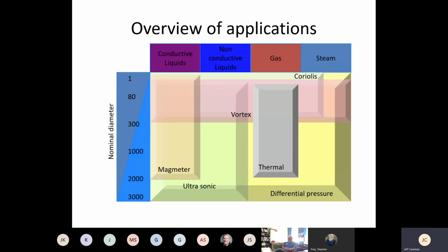So we take all these meters and we can kind of put it into a chart and look at some of our solutions that we have out there to offer. Under conductive liquids, you can see a mag meter really exists in this world. Conductive liquids only, has some limits on temperature, but really has unlimited size ability. We manufacture magnetic flow meters from a 1/12 of an inch on up to over 100 inches. I think 108 right now is the biggest one that we've made. So mag meters can fill a nice niche, especially if it's a big line, which most big lines are conductive. It's wastewater, but it's obviously got to be a liquid.